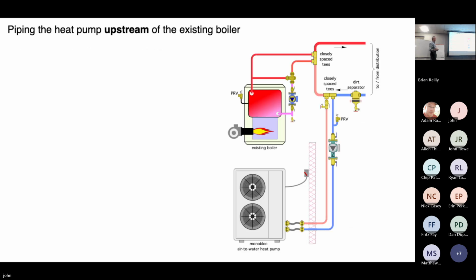Okay. Here's another possibility where you're using what's called primary secondary piping, and that ties each heat source in with a pair of closely spaced T's. What these closely spaced T's do is they decouple the pressure dynamics that this circulator is creating from this circulator, as well as from out here. There's going to be at least one other circulator. So we call that hydraulic separation.